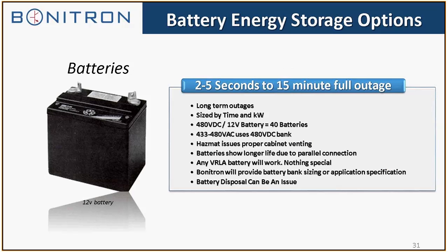It's fairly common. A little quick review about batteries, and then we'll move on to something else here. The only other thing that I haven't pointed out before is battery disposal can also be an issue. Usually you're not worried about that. Between 3 and 5 years, battery string changeouts usually occur depending on the battery manufacturer. They say 5 years. When I talk to the plant people that have batteries they're using for ride-through or for UPSs, they usually end up changing them out around 2 to 3 years, depending on how beat up the system gets or how many times the UPS is activated or the ride-through is activated.